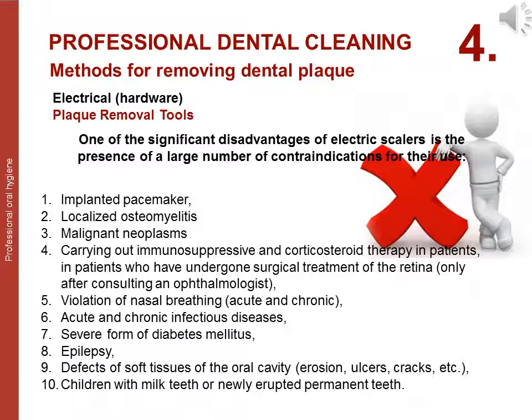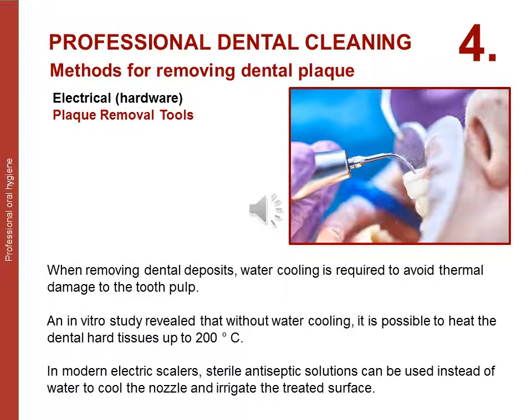Contraindications for electric scalers include: implanted pacemaker, localized osteomyelitis, malignant neoplasms, immunosuppressive and corticosteroid therapy, nasal breathing obstruction, acute and chronic infectious diseases, severe diabetes mellitus, epilepsy, defects of soft tissue of the oral cavity, and children with milk teeth or newly erupted permanent teeth. When removing dental deposits, water cooling is required to avoid thermal damage to the tooth pulp; without water cooling, dental hard tissue can heat up to 200°C. In modern electric scalers, sterile antiseptic solution can be used instead of water to cool the nozzle and irrigate the treated surface.